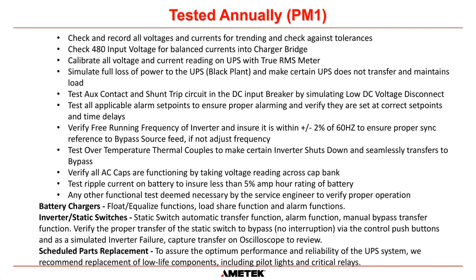We also check the input to our chargers for balanced current into the bridge. In any three-phase charger bridge, the input current to the SCRs on each phase should be very, very balanced. They should be pretty much identical. So if there is unbalanced current into the charger bridge, that probably means that there is an SCR that is not being fired correctly.